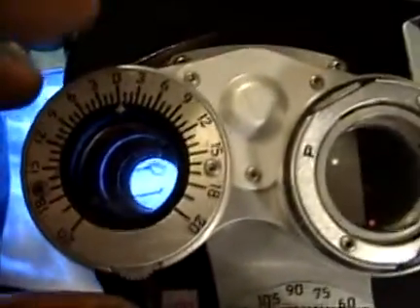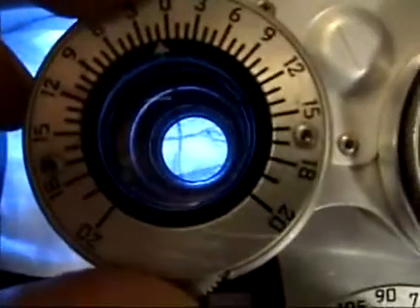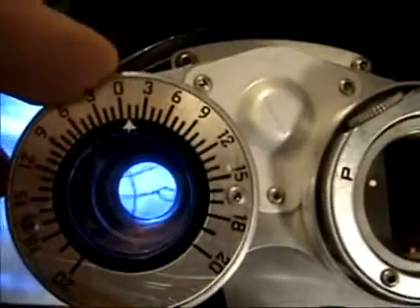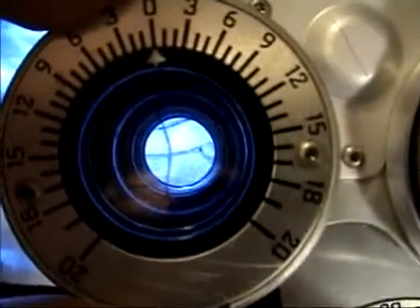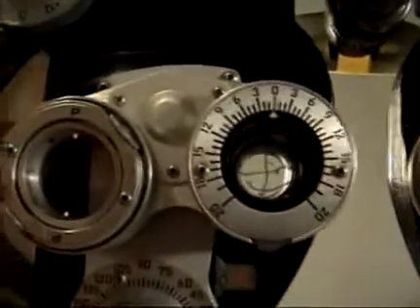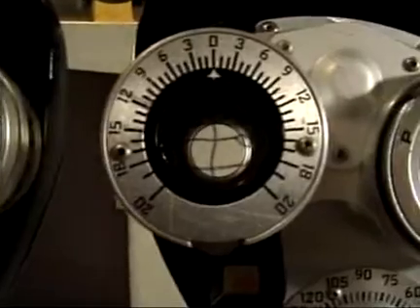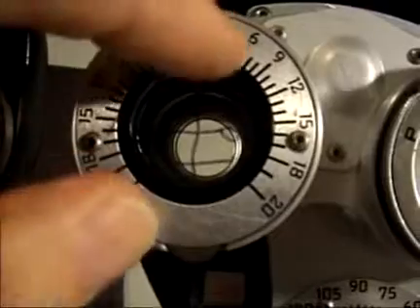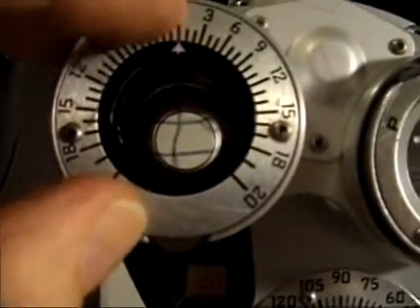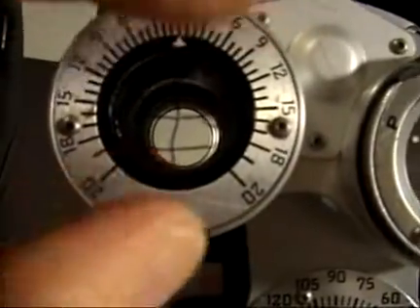It's often useful to have little trays — like cupcake trays — to hold small parts during disassembly. With it back together and checking the alignment, it was definitely off at one, then off at two, so I rechecked the optical alignment. Now reassembled, I found a good optical alignment and zero set on both of them. I played a little bit with the plate alignment — you can shift the plate up, down, side to side, rotate slightly, or even enlarge the hole slightly if you need a bit more play.